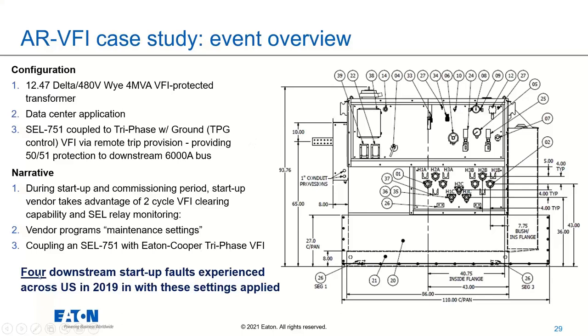And just as a reference point, we did have this particular customer that had this event. This happened 4 different times during commissioning events. You might think, I was referring to the primary side settings having to be coordinated for transformer inrush, and yeah, that's only relevant when I'm starting up the transformer. But startup and commissioning is one of the most risky times for incidents. That's when things are being tested initially. Things may not be fully tested or maybe there are errors. That is one of the very risky times.